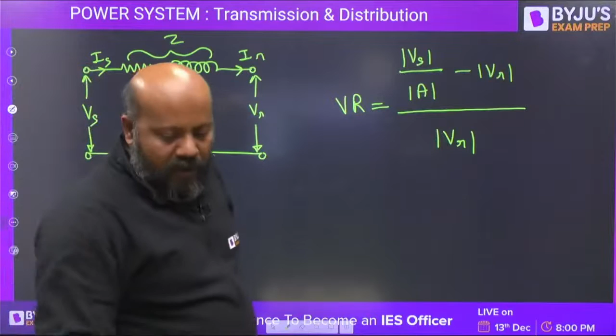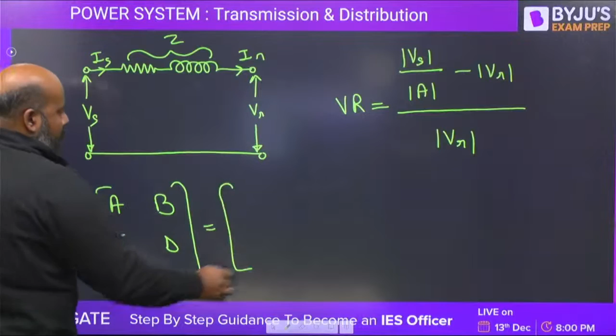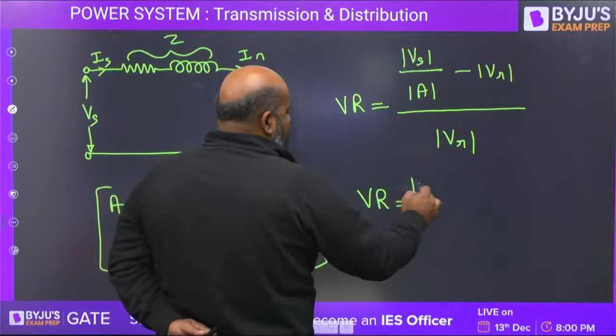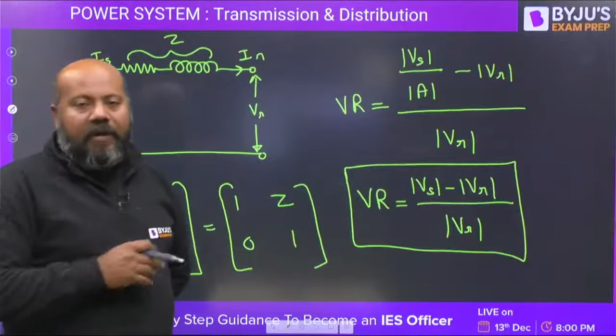If you see a short transmission line, what is going to be the ABCD parameters? It is going to be 1, Z, 0, 1. It is simply a series impedance. So, A value is going to become 1. So, voltage regulation will simply be mod Vs minus mod Vr, upon mod Vr. Now, there are two ways in which you can find the sending end voltage and then the voltage regulation. One is, you simply write Vs is equal to AVR plus BIR. A is 1, VR you know, B is Z, IR you can calculate.